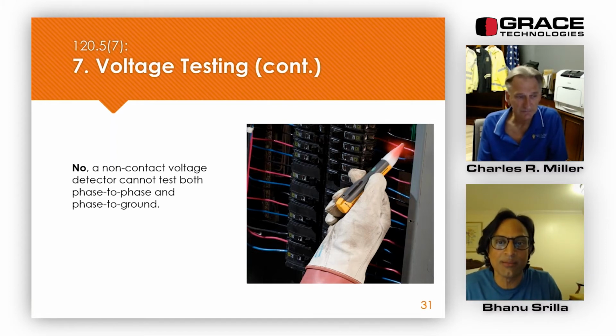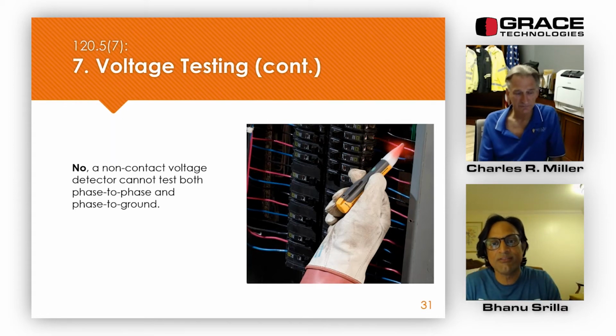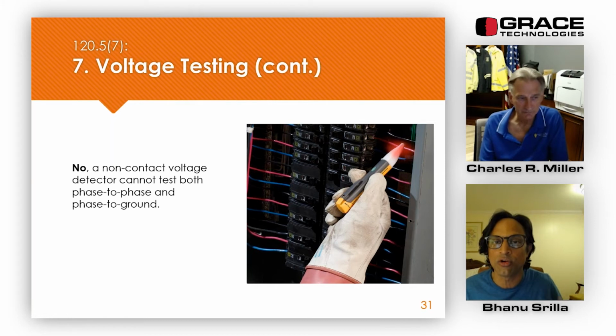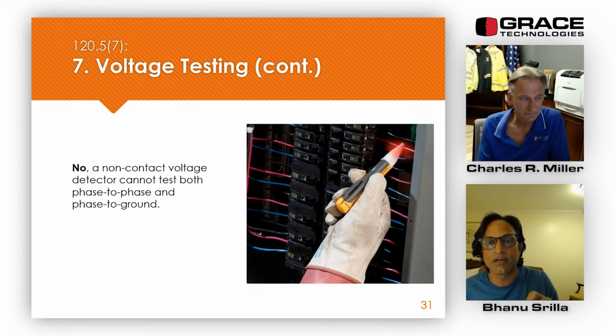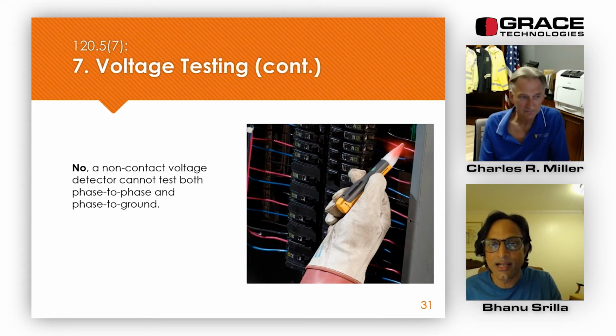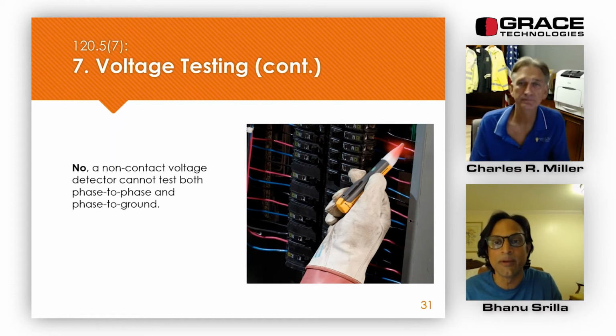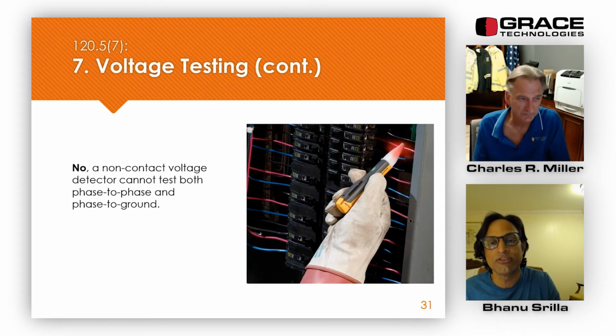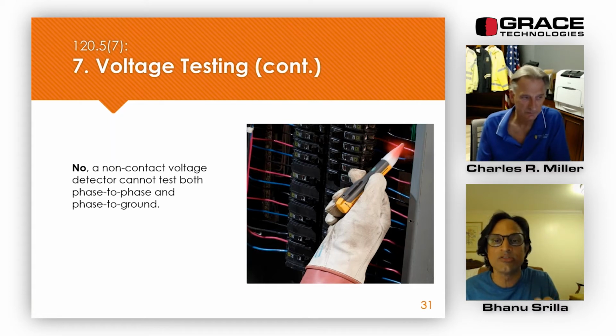So the safe test points, which Charlie mentioned before in previous slides, are built into the high impedance protected circuit. You can safely verify the voltage absence from outside the door without getting a max fault beyond 3.5 milliamps. Your max exposure, even if you accidentally put a paper clip and short it together, will not exceed 3.5 milliamps. Again, these are all listed and labeled by UL for 61010 standards. That is measurement, testing, and signal generating equipment, which is the same as your voltmeters or your Fluke meters, which Charlie showed in previous slides. So please don't confuse this device. What we're showing on the screen is not meant for absence of voltage testing, and this is only used for enhanced mechanical lockout tagout for task-qualified personnel.